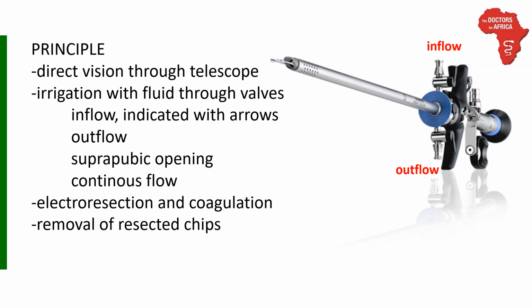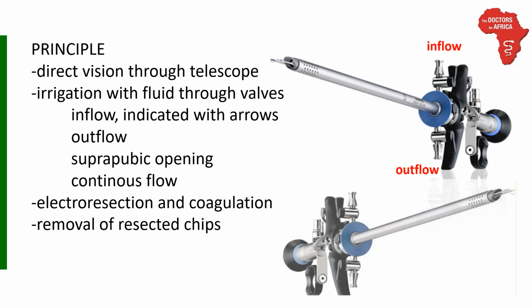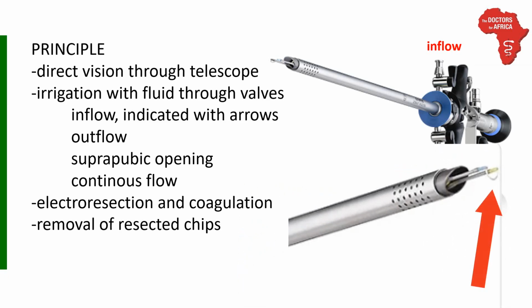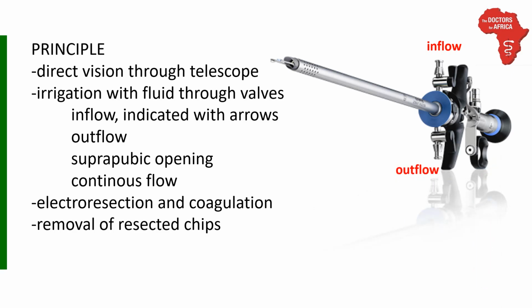Continuous flow can be obtained by placing a suprapubic catheter that is used for continuous outflow of the irrigation fluid. But with this typical instrument with continuous flow, you have inflow through the tube and outflow through the small holes you can see at the tip of the instrument. In this way, you do not need to place a suprapubic catheter. With the small semicircular wire at the tip of this instrument, you can heat up and resect the tissue and coagulate the bleedings. At the end, the resected chips need to be removed through the instrument using a special syringe.